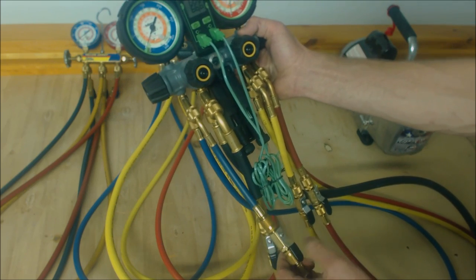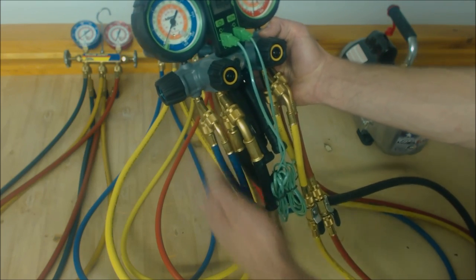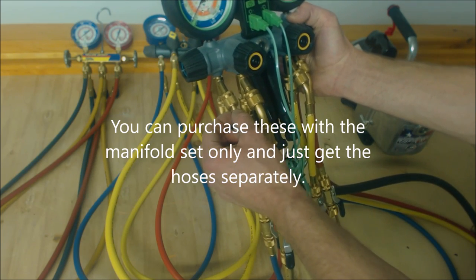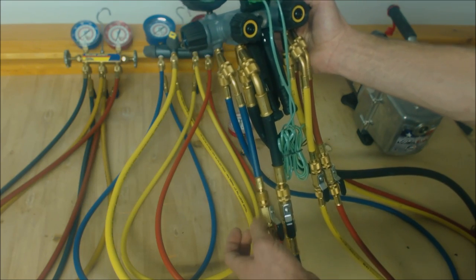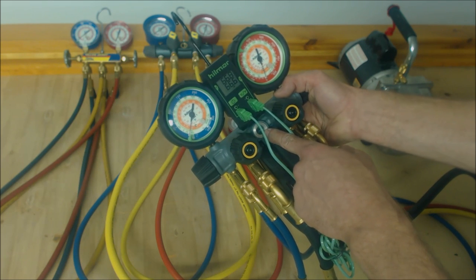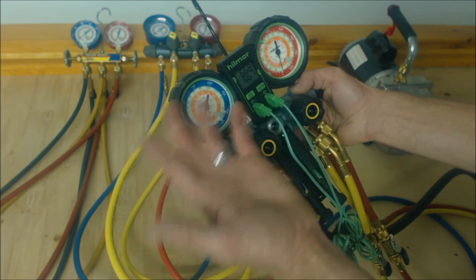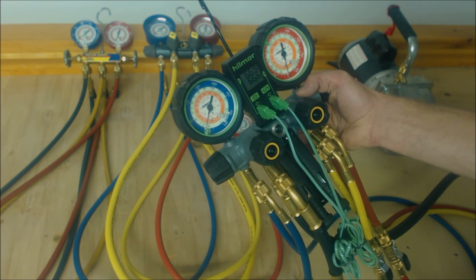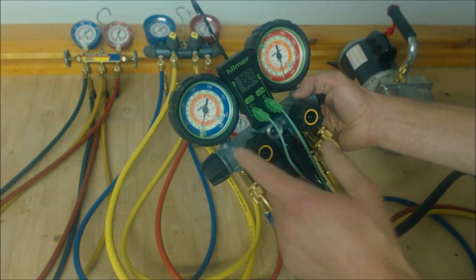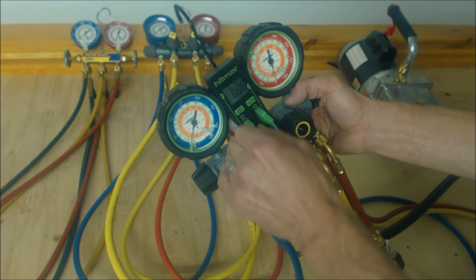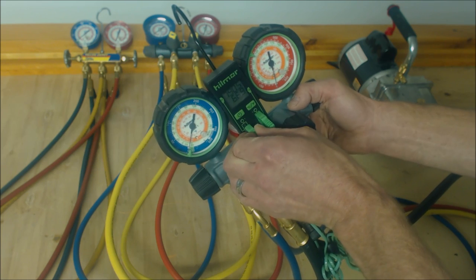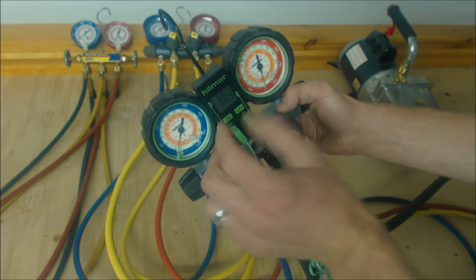A lot of times I put Armaflex over the temp sensor regardless of whether it's a clamp or a small K-type thermocouple that you see that I use with my UEI multimeter. But this is a very good set as well. The only thing with this set is they do sell this set with hoses with this extra section of hose. I don't necessarily like that with the valve. I like to have the valve all the way at the end with no other possible leaking points like this. Once again I don't use this liquid line sight. As far as accuracy, this set is just as accurate as the yellow jacket it seems. I don't know about life expectancy on these because these are newer. But I do like to use these periodically. The temp sensors - you have to push in hard so there is no missing the connection. It is a very tight electrical connection.